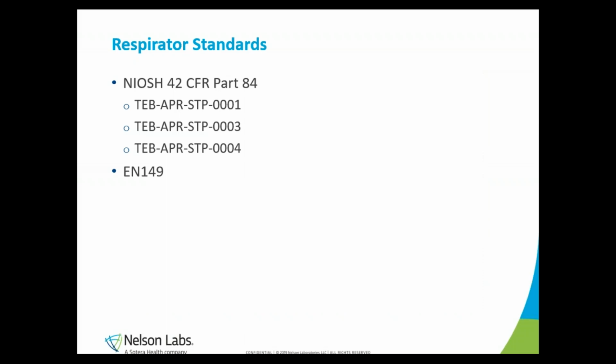There are two respirator standards that we'll mention. One is the NIOSH standard, 42 CFR Part 84. This is a consensus standard that tells the requirements for the face mask. It does describe the testing somewhat, but the TEB standards below are the three standards which describe in detail the testing for filtration efficiency, inhalation, exhalation resistance, and valve leak testing in the US.